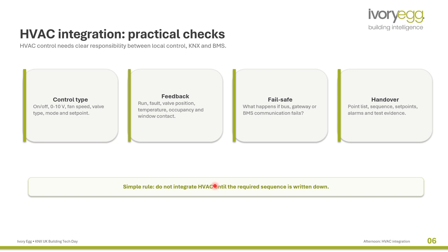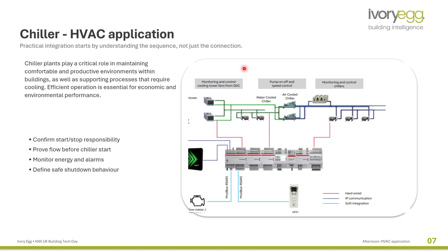So when we talk about HVAC in the plant room, we talk about complex topology. For example, you can see the chiller schematic in these pictures. We want to control it, so we should have the right sequence of control. For example, start the pump, prove the flow by the sensor, start the chiller, control temperature by the sensor, sequence chiller, monitor energy, generate alarms, and safe shutdown. We should be prepared for that in the controller.